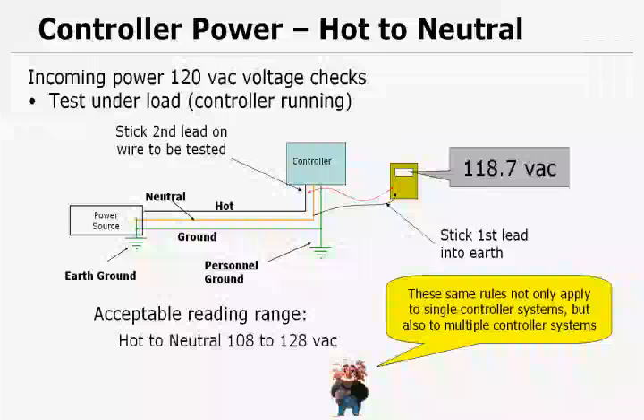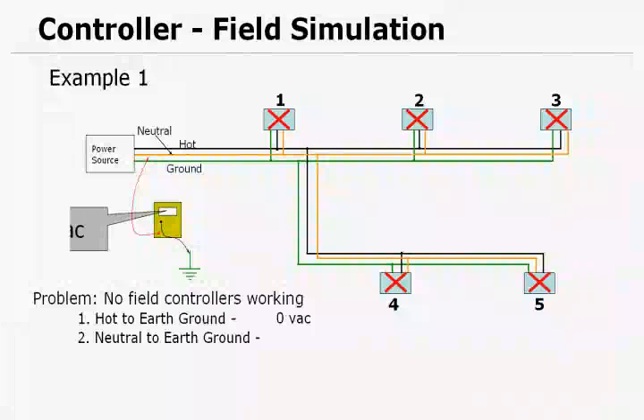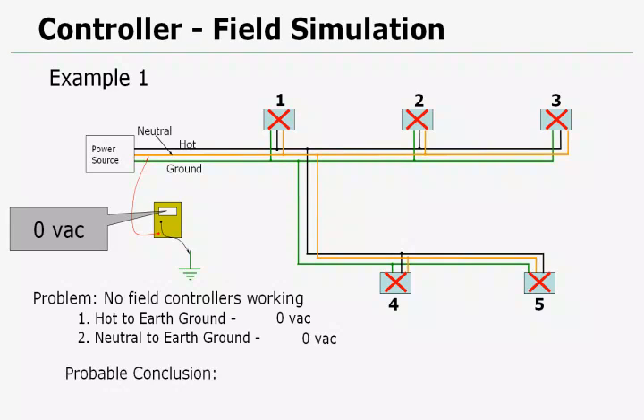Let's do a quick field simulation. Here's our problem: no field controllers are working. In this example, we've got five controllers. So we're going to take some readings, the same readings that we just took. Hot to earth ground, 0 volts. So we know we've got that reading. Neutral to earth ground, 0 volts. Right now we'd come up with a probable conclusion that we have no power coming out of our power source. Logically we'd go to the power source and see if we have power into it, if it's a breaker turned off, a fuse is blown, or just what's going on at the power source. So that was example one.